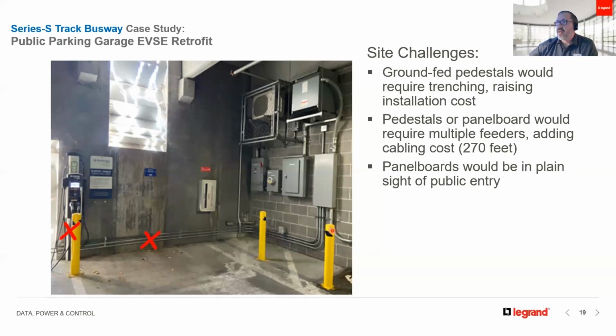I'm jumping ahead a little here, but I'll try to explain. The other constraint is that the electric chargers they're going to add are located 270 feet away, about 82 meters, from this point. So when you get into power distribution basics, when you distribute voltage from one place to another, you have impedance, which is the resistance of the current or power to travel. So you have to size your system for that, using bigger, more costly cable. If you have a panel board or breaker here, you need one pipe and wire running to each EV charger located 82 meters, 270 feet, away.